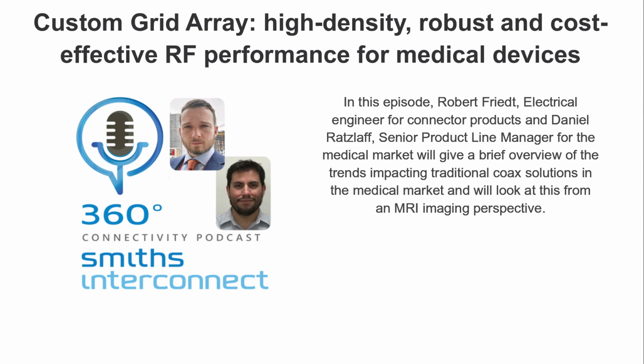So how does this impact the connectors used on these systems? The biggest impact is that there is much less space for traditional interconnect solutions, both internal and external connections, due to the size. This means smaller connectors that can use the space available, even if it's in a non-traditional shape or size. They also provide improved imaging quality versus older systems due to the increased field strength. Now, this is true for new high field strength MRIs as well, where you get better and better images and improved comfort, so a win-win. And lastly, they tend to have faster turnover times versus traditional MRIs due to the ease of use and the fact that patients tend to hold still better, preventing delays in the procedure.